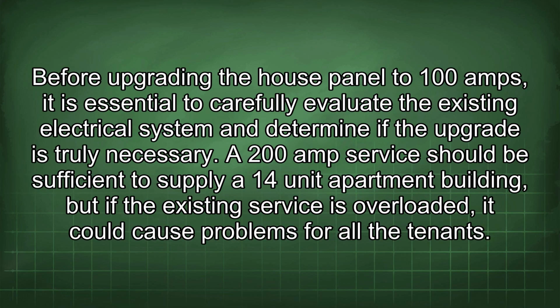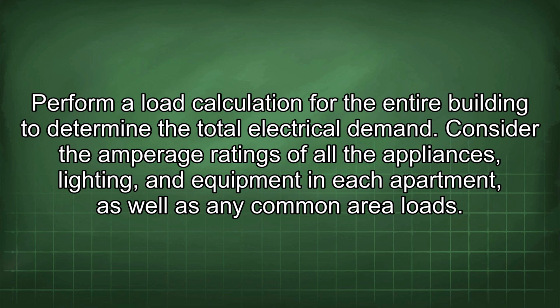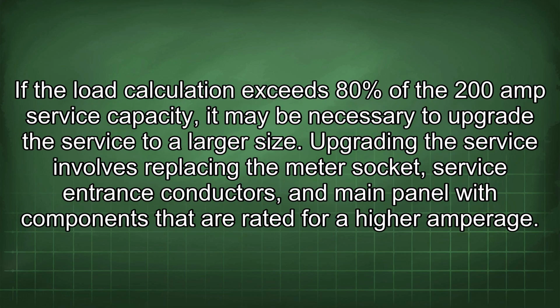Before upgrading the house panel to 100 amps, it is essential to carefully evaluate the existing electrical system and determine if the upgrade is truly necessary. A 200 amp service should be sufficient to supply a 14-unit apartment building, but if the existing service is overloaded, it could cause problems for all the tenants. Perform a load calculation for the entire building to determine the total electrical demand. Consider the amperage ratings of all the appliances, lighting, and equipment in each apartment, as well as any common area loads. If the load calculation exceeds 80% of the 200 amp service capacity, it may be necessary to upgrade the service to a larger size.